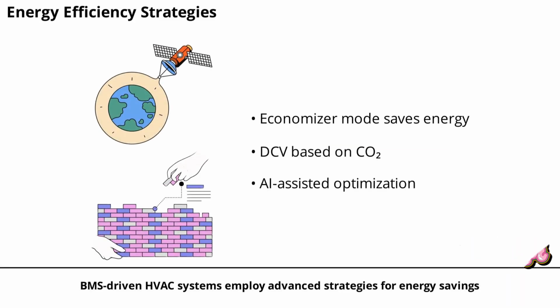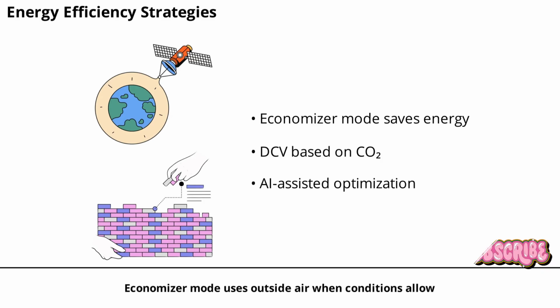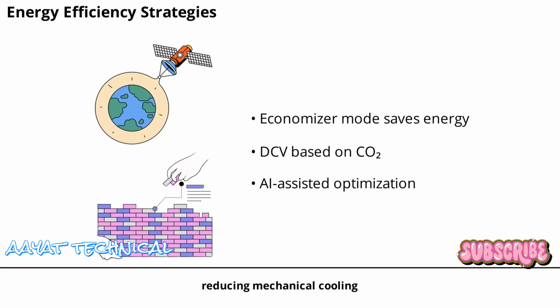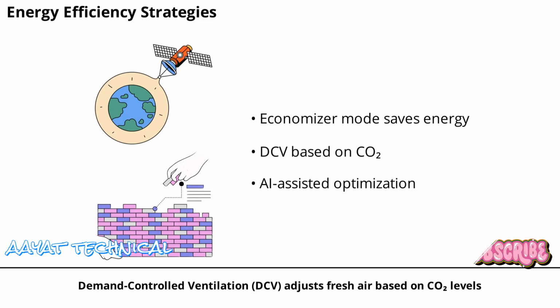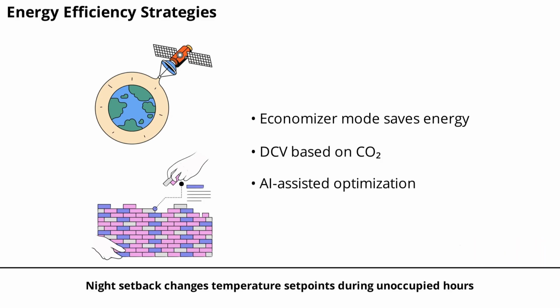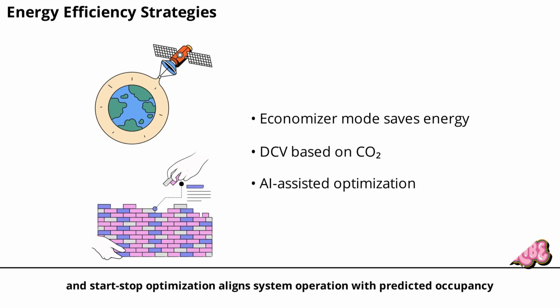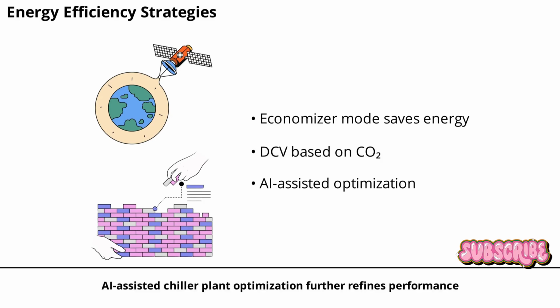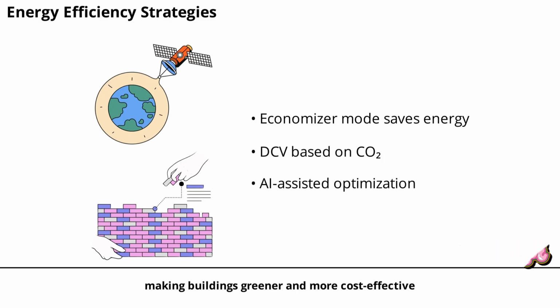BMS-driven HVAC systems employ advanced strategies for energy savings. Economizer mode uses outside air when conditions allow, reducing mechanical cooling. Demand-controlled ventilation, DCV, adjusts fresh air based on CO2 levels. Night setback changes temperature set points during unoccupied hours, and start-stop optimization aligns system operation with predicted occupancy. AI-assisted chiller plant optimization further refines performance, making buildings greener and more cost-effective.